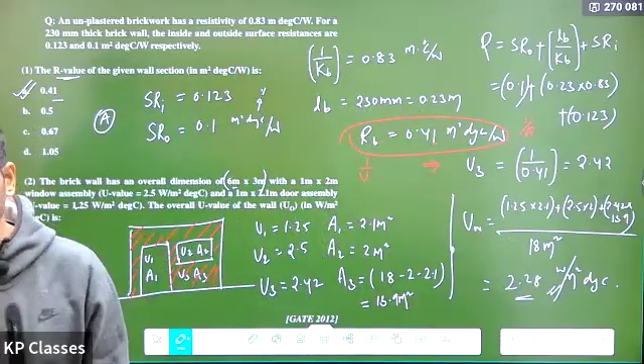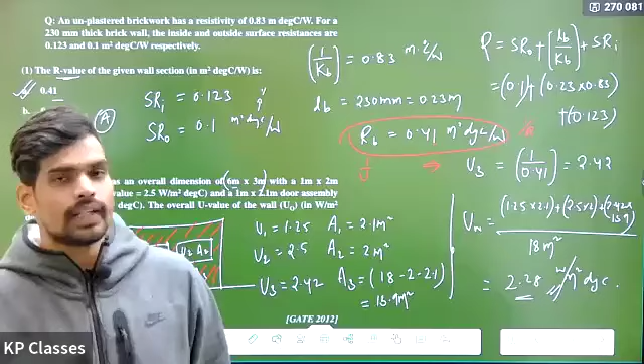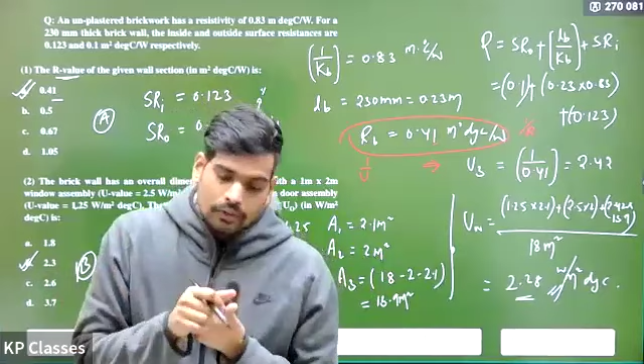Thermal conductance and thermal transmittance used interchangeably? Yes, they are similar, but not exactly the same. You can use them interchangeably, but the only difference generally is that thermal conductance is a term you use for one particular layer. You don't use it for the overall wall. And U value, that is thermal transmittance, you measure air to air generally for the overall wall. That's the only slight difference, but the measurement unit for conductance and transmittance is the same. It is watt per meter square degree centigrade in both.